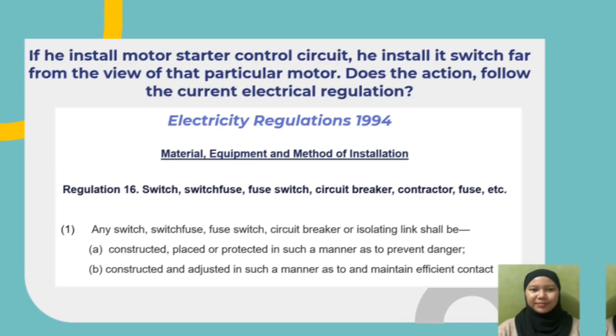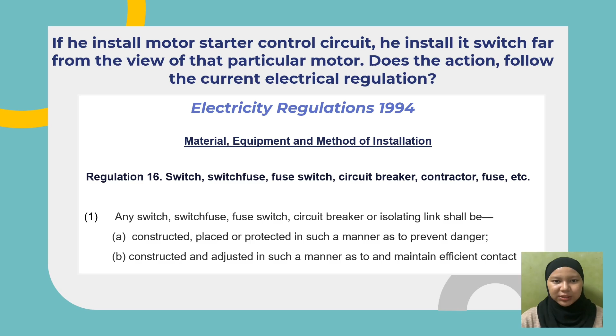Based on the Electricity Regulations 1994, the suitable regulation for the question is under Material, Equipment and Method of Installation, Regulation 16, which covers switches, switch fuses, fuse switches, circuit breakers, contactors, and fuses. Regulation 16(1) states that any switch, switch fuse, fuse switch, circuit breaker or isolating link should be (a) constructed, placed or protected in such a manner as to prevent danger, and (b) constructed and adjusted in such a manner as to maintain efficient contact.